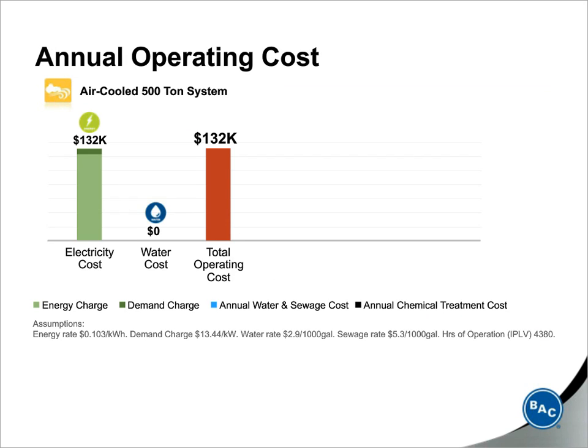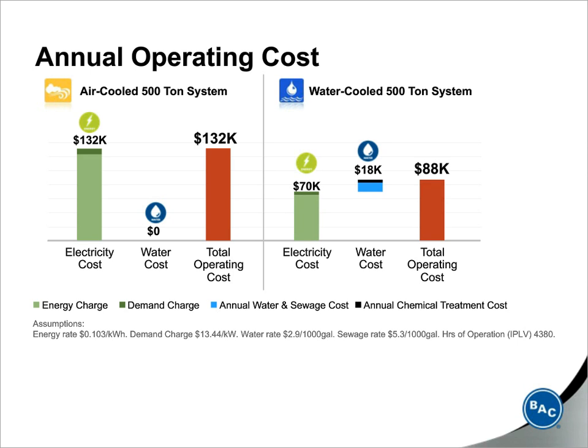So I just want to expand on this point for a moment. Here's a typical 500-ton system. An air-cooled system, typically, this particular air-cooled system costs about $132,000 in energy usage. And again, no water is consumed on site with the air-cooled system. Now, if we compare this to a water-cooled system, which costs $70,000 in electricity and $18,000 in water costs, and the water costs include evaporation, blowdown, and water treatment as well, that's a total of $88,000.